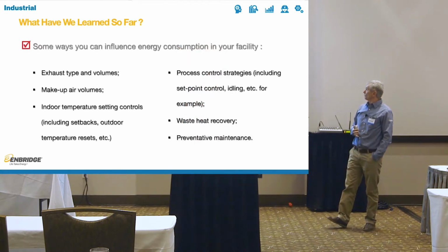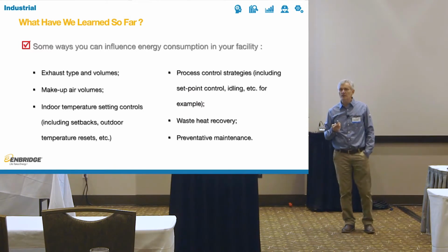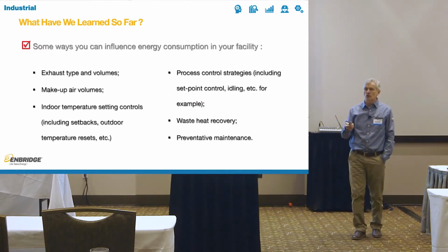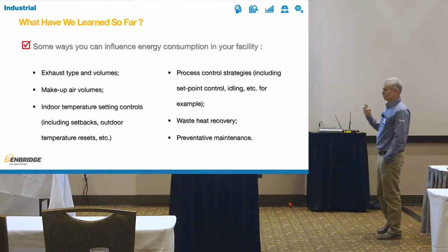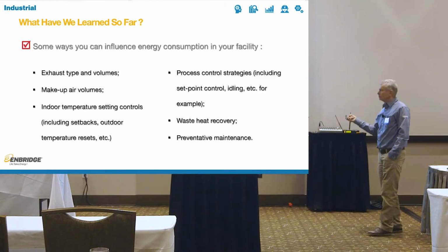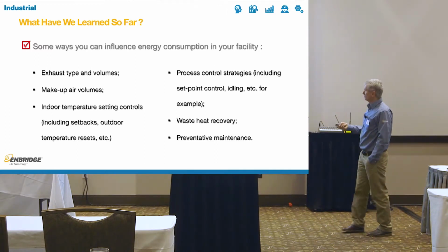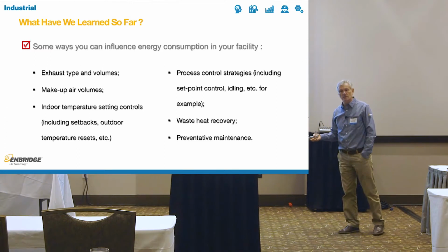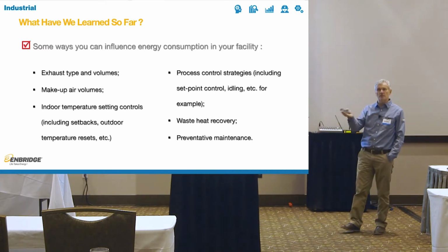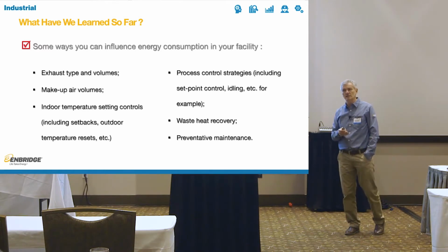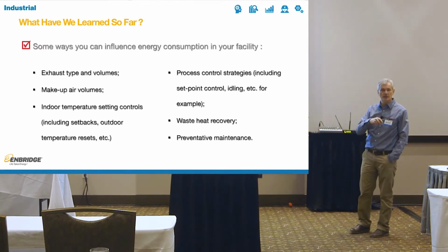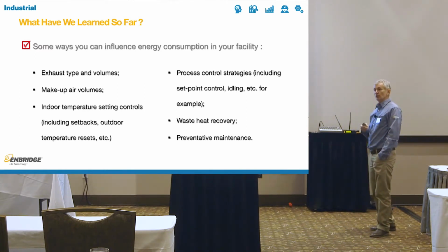So what have we learned so far? What are the ways you can actually influence energy consumption in your facility? Exhaust, type and volume, makeup air volume, indoor temperature settings. Lots of people have the same setting whether they work or not. Even when the facility is empty on the weekends, they still leave everything operating, including the makeup air units, which is really odd.